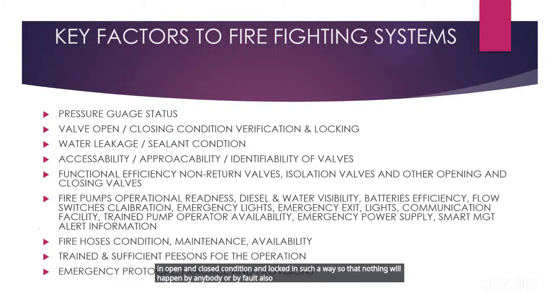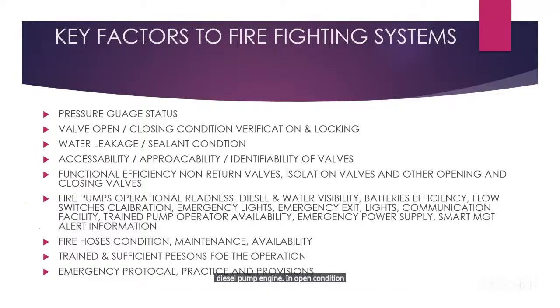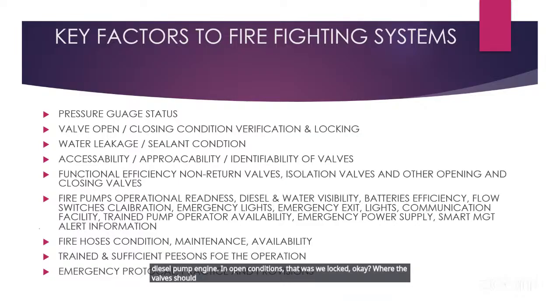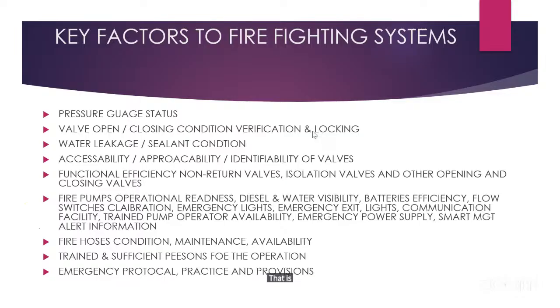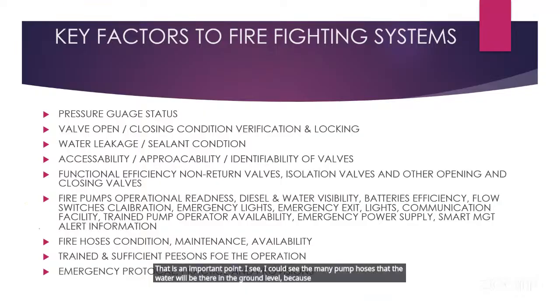For example, suppose the diesel valve should be kept open from the diesel tank to the diesel pump engine. In open condition, that must be locked. Where the valve should be closed, that valve must be closed and locked. And verification of locking should be there. And water leakage is an important point. I have seen many pump houses where water is on the ground level because whenever the pump started, there was water leakage from the sealant. See, water leakage must be there, but at a permitted level.